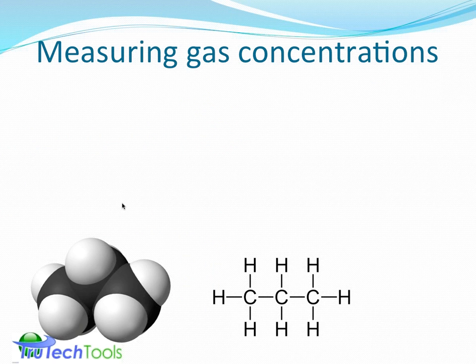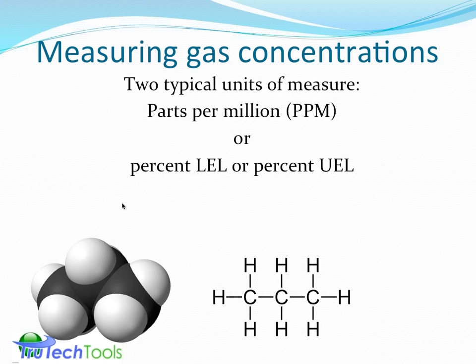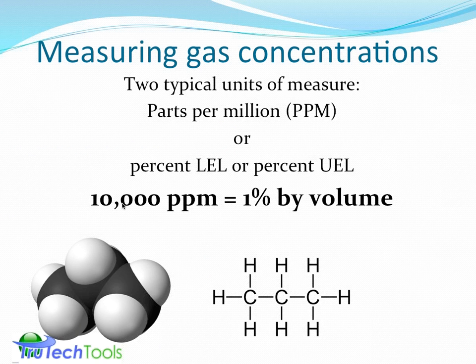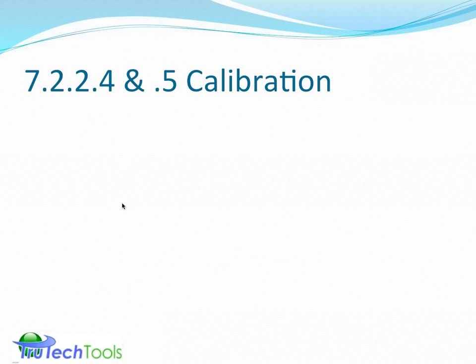Okay, so let's take a look at measuring gas concentrations and get into a little bit more of the measurement science here. The typical unit of measurement is a part per million. It's a volume concentration. It's how many parts in the whole, how many parts are in the sample. It can be expressed as a percent LEL or percent UEL. Again, ppm can be converted to percent LEL or percent UEL if you know the gas, because propane and methane have different explosive limits. And just for reference, 10,000 parts per million is a 1% level by volume. And a part per million, again, can be correlated with a percent gas.